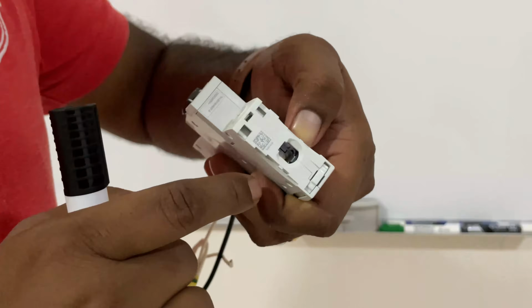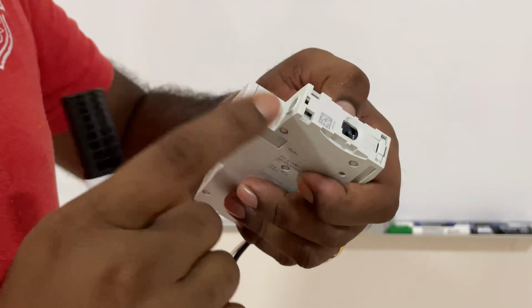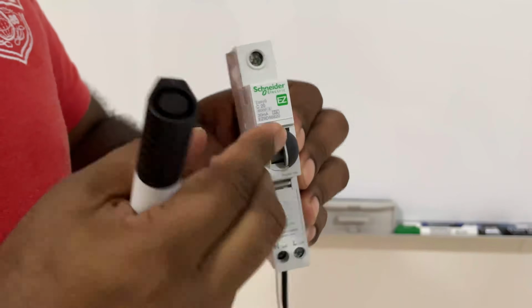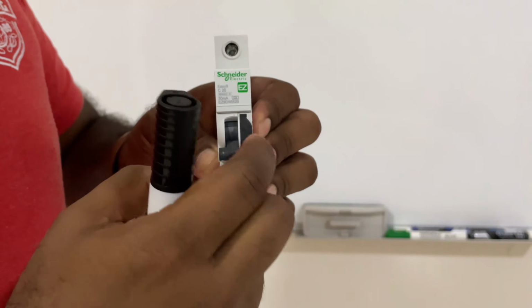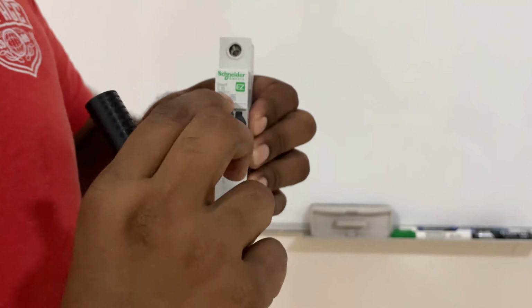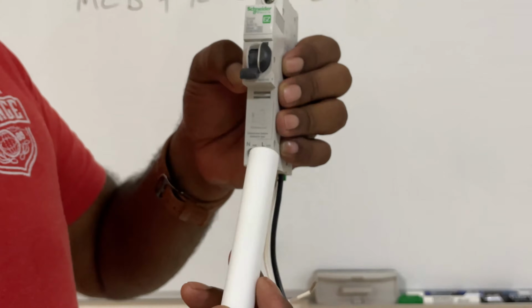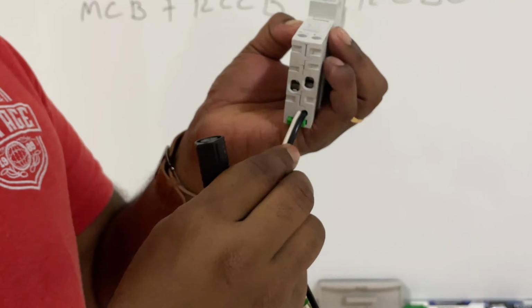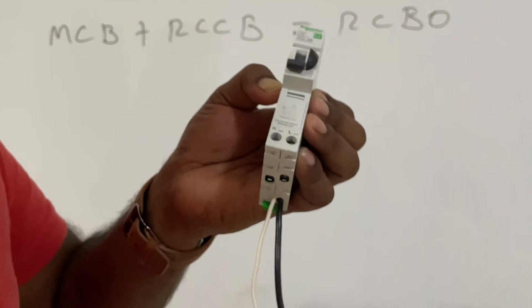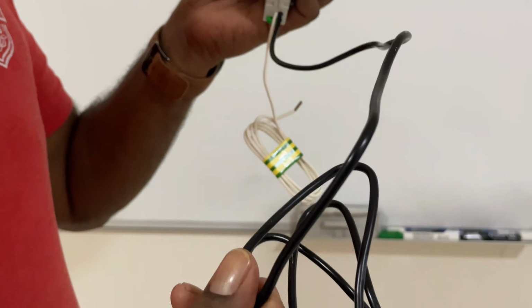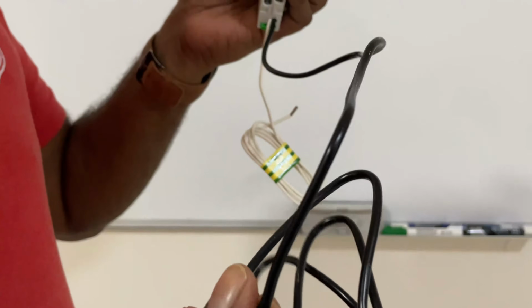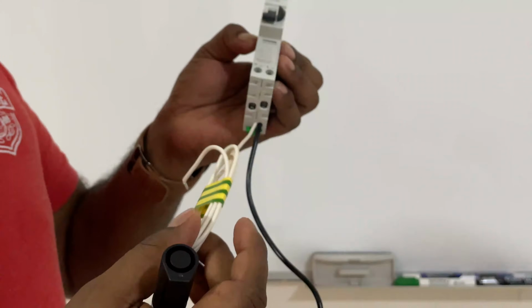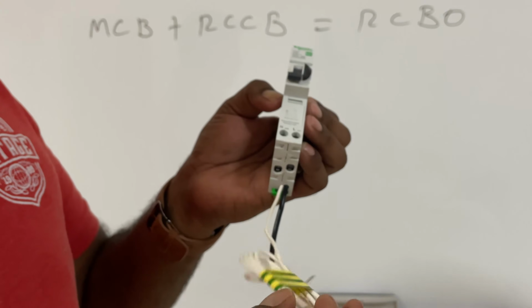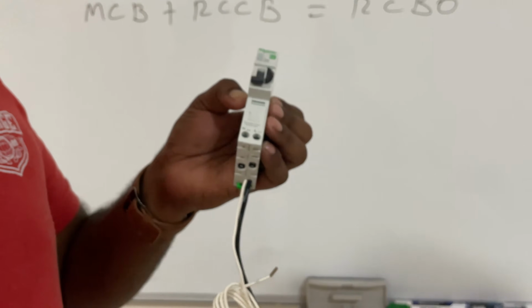Also we can see how it is designed. There is one terminal for the incoming phase, where we can connect the incoming phase, and there is an on off knob. Next to on off there is a test button. By pressing this we can test whether this RCBO is tripping or not. Down you can see neutral and line outgoing terminals. There is also an incoming neutral terminal, which is to be connected to neutral. Also there is an earth connection, which is also supposed to be connected to earth. We will see how this works and why the earth is connected to the RCBO.